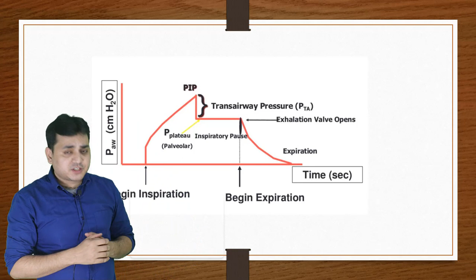Correct? So now let's discuss the low minute ventilation alarm or the low pressure alarm. So we have set a pressure, tidal volume. So if it is coming low in the ventilator alarm, that means the pressure is leaking from somewhere, the volume is leaking from somewhere. So find out, is there any circuit disconnection? Is there any loose connection? Is there any cuff leak? All these things you have to find out, whether you have set the flow inadequately. If these things are there, water traps there, then the solution you have to choose accordingly.